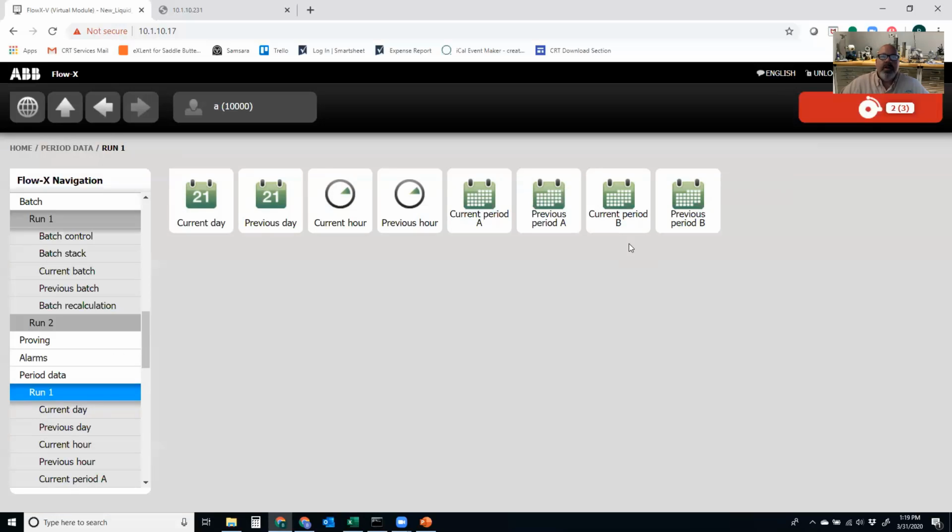So you can set these up where I'm doing a batch every day at midnight, but my day ends at 6 o'clock in the morning. So I have a day running from 6 a.m. to 6 a.m. And then I can set period A up for, let's say, if my customer's day runs from midnight to midnight, I can set up another set of flow weighted averages and totals for the customer that run from midnight to midnight. And then if I have a whole month's worth of data, I can set up another period where I have totalizers and flow weighted averages for the entire month, where at the end of the month it stops and then puts it in the previous.